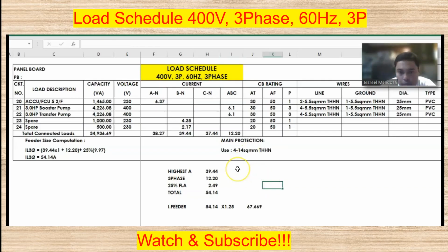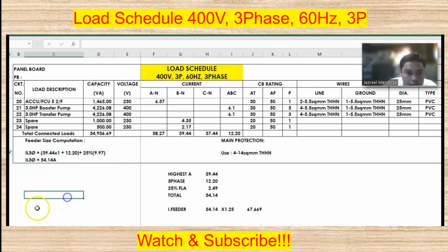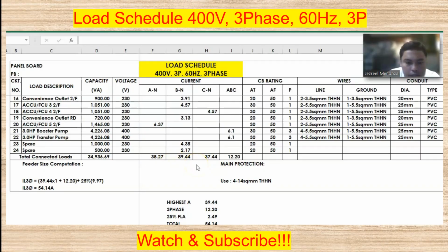So, and then for the main protection, what main circuit breaker do we need to use? Okay, the next for 54 is 60 amperes, but we can use 70 amperes for future expansion or merong additional na loads. So our main will be a 70 amperes circuit breaker. We have 400 volts and then 3 phase, then 60 hertz. Okay, so this will be our main circuit breaker.